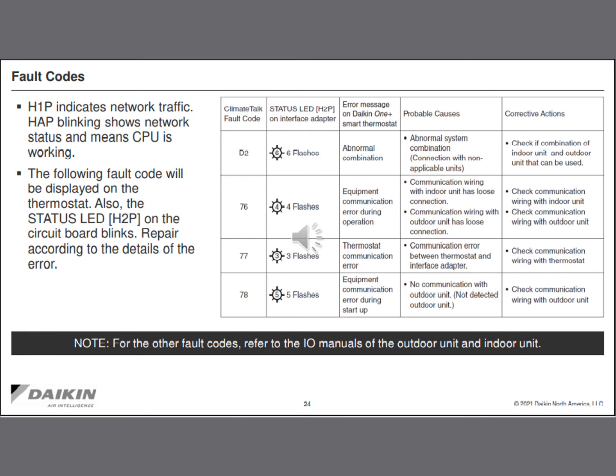And just bear in mind, if you happen to have an ignition failure or a pressure switch failure, any type of failure that involves your gas furnace, you will not be able to access those failures via the Daikin 1 thermostat. You can only access those errors through the PCB on your furnace control. You don't quite have that luxury without the communicating abilities with that furnace.